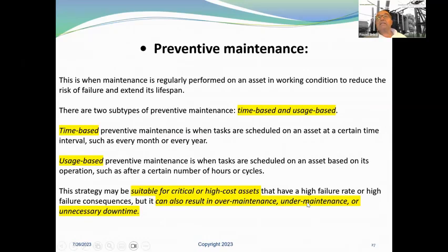It's exactly what happens when you have a good maintenance program but you don't know: a lot of times you touch some transformers or breakers that do not need to be opened because they're in good health, in good condition. So this is the risk with this strategy, and I have seen it many times.